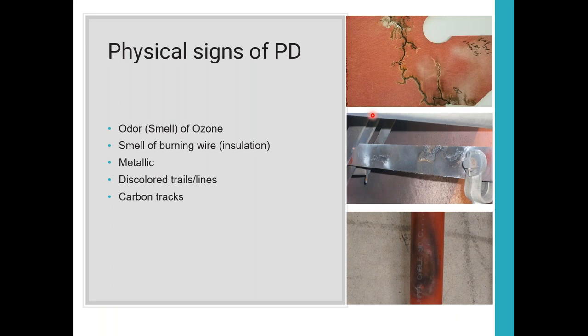Physical signs, as I said, smell of ozone. When you open up a cabinet door, if you get the smell of ozone, if you have vacuum bottle circuit breakers or you haven't had a breaker operate in a long time, you shouldn't smell ozone.